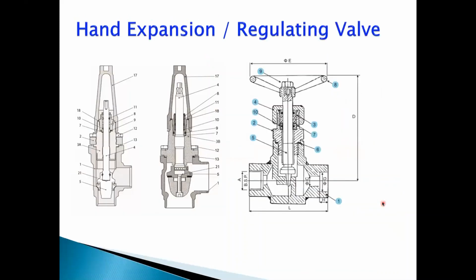Then, like we talk about thermostatic expansion valves or the motorized expansion valves, the most popular parts are the hand expansion valves, or so-called hand regulating valves. In hand expansion valves, you can have a cone type valve, or a needle type valve. The needle type valve is more accurate for giving you a higher pressure drop, and it can be very precisely adjusted. The function of the expansion valve is to drop the high pressure coming from the liquid to the desired temperature.